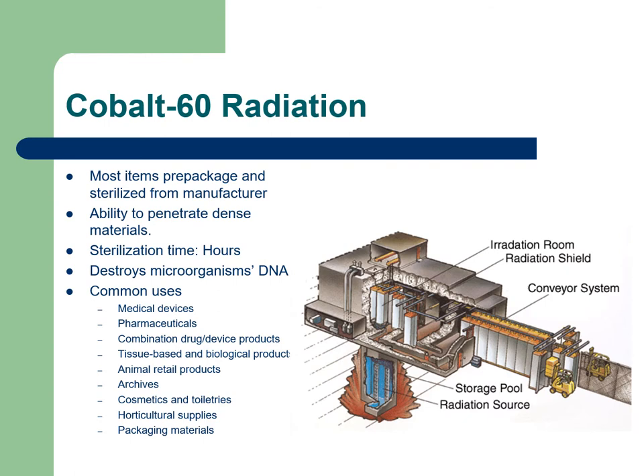Lastly, bringing up the rear is cobalt-60 radiation. This isn't typically done in-house—this is what the manufacturer does. So most of the disposable things that come into the hospital prepackaged and sterilized are sterilized using cobalt-60 radiation. It is gamma irradiation, and they say it is safe. It works well for penetrating dense items, so items we couldn't sterilize with other methods, gamma irradiation is capable of doing. The sterilization time varies depending on what they're sterilizing and how dense it is.